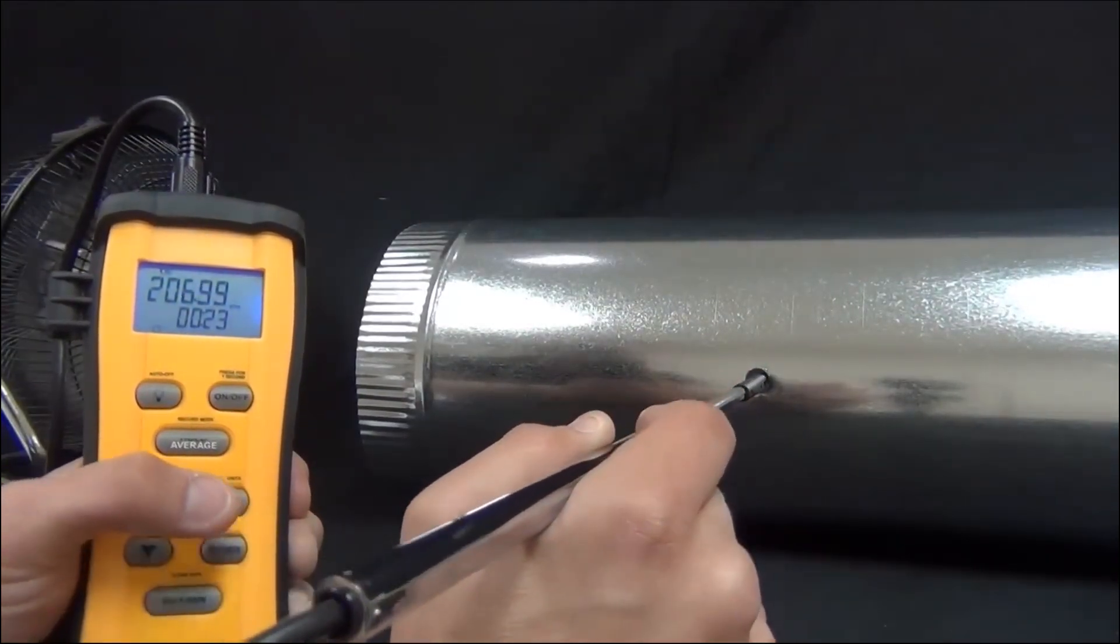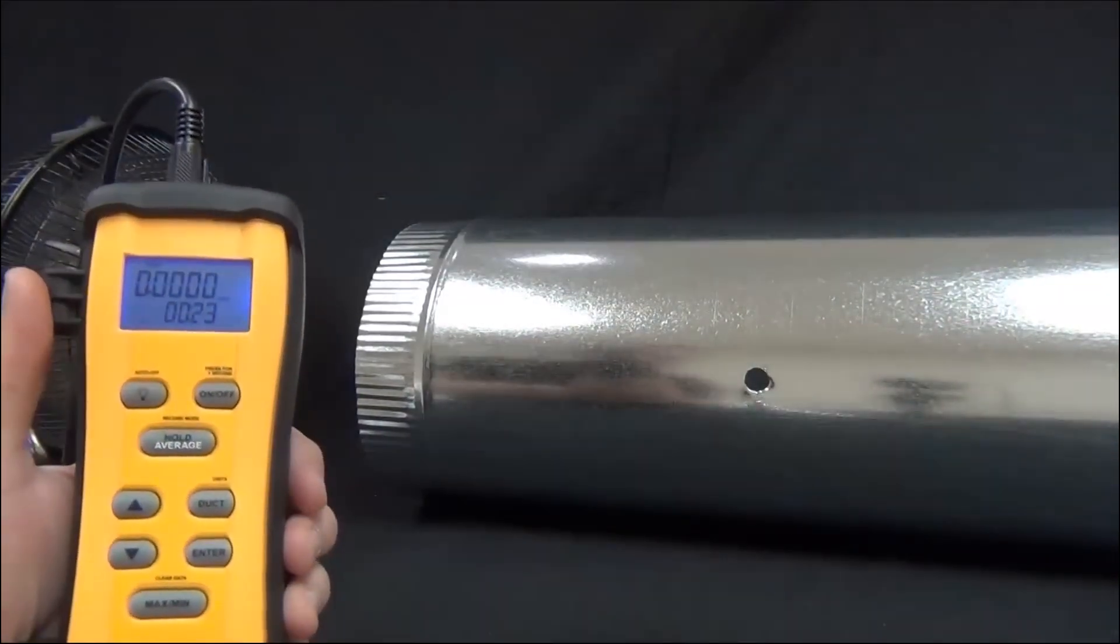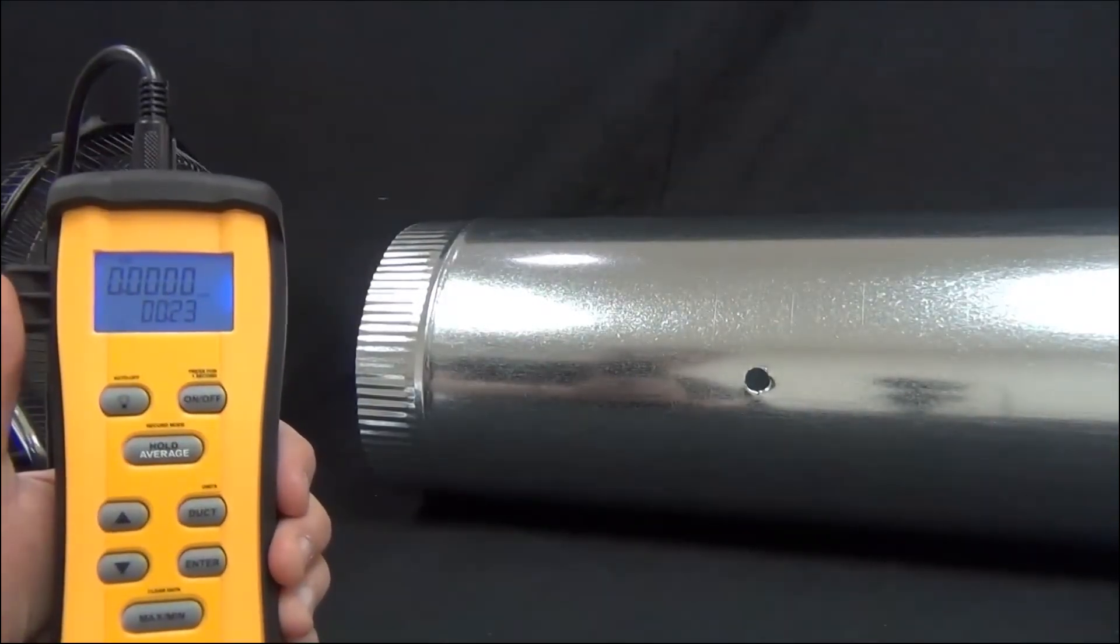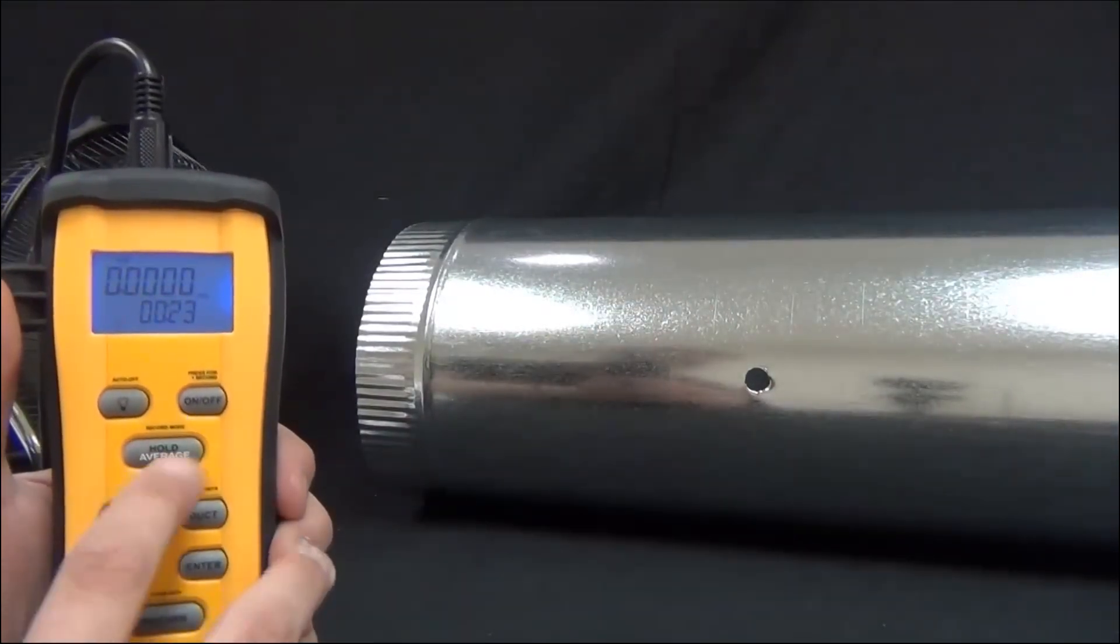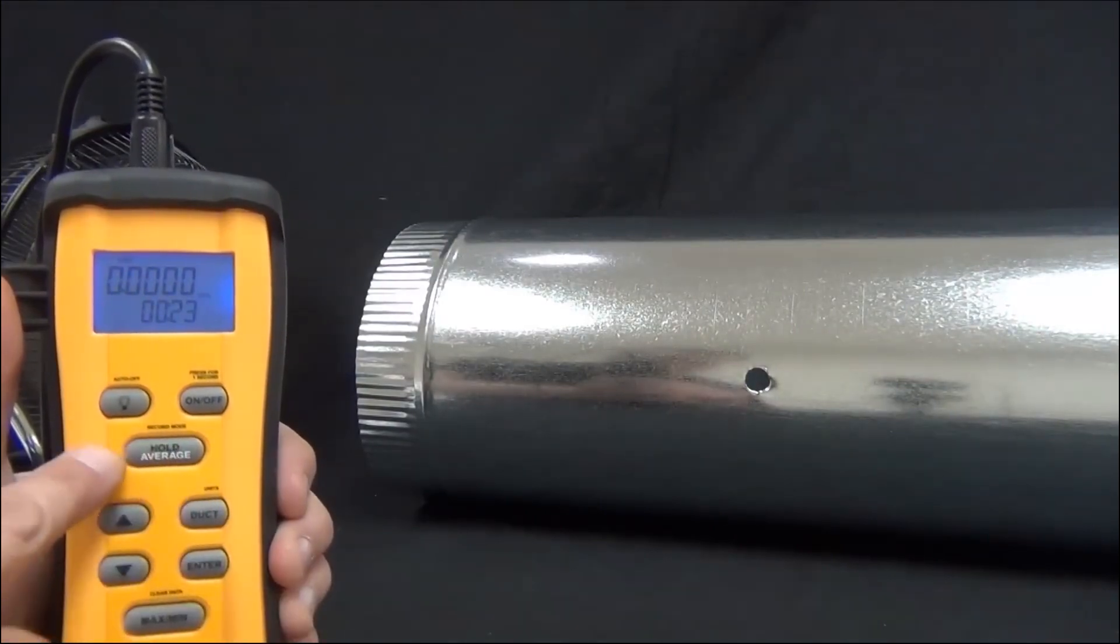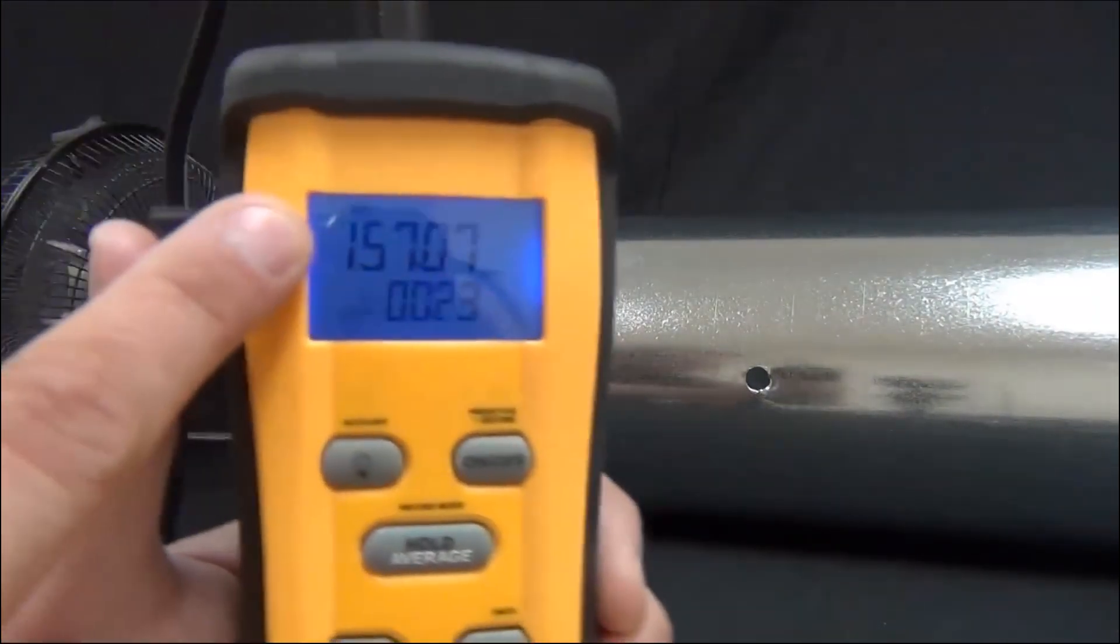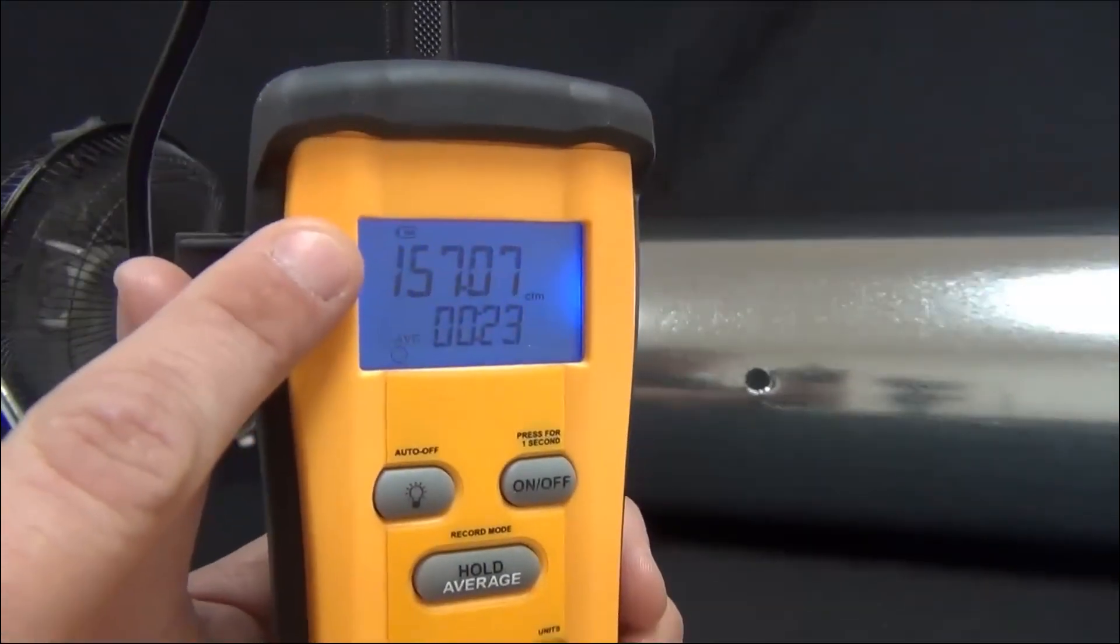So yeah, you'll see that we're reading zero CFM because we're not in the duct anymore. But to get the average, I'm just going to press average once, and it'll give me an average CFM of 157 across that duct. And we did it over a 23 second time span.